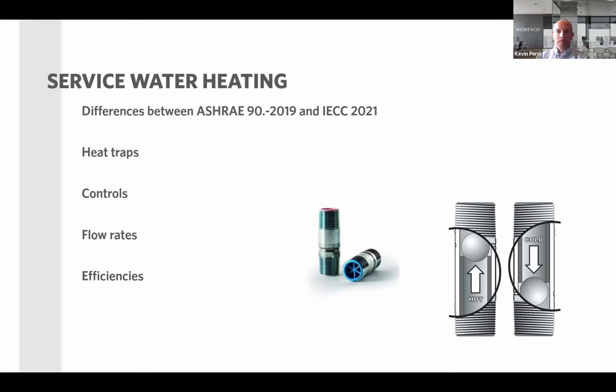Then we go to controls. Storage temperature controls, 100 or 120 degrees or lower. Automatic time switches or other controls to turn off systems during extended periods of time when hot water is not required. Outlet temperature controls, 110 degrees or lower, and circulation pump controls. So these are the controls and differences between the two, IECC and ASHRAE. So just know that IECC does require some different controls based on their storage temperature than ASHRAE does.